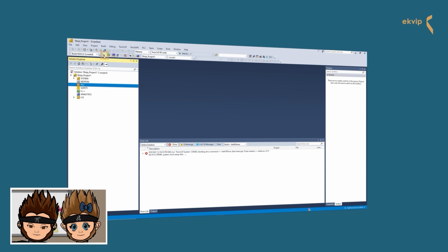Next we have the Activate Configuration icon. If you click on this icon, the whole system configuration will be downloaded and compiled, not only the Ethernet configuration. This includes, for example, different cycle time settings, licenses, task settings, and so on. Next to the Activate Configuration icon, you see two very similar buttons. The green one is the Restart TwinCAT System button and the blue one is the Restart TwinCAT in Config Mode button. Both have something to do with the runtime mode. And I think this is a good moment to explain the different runtime modes to you.